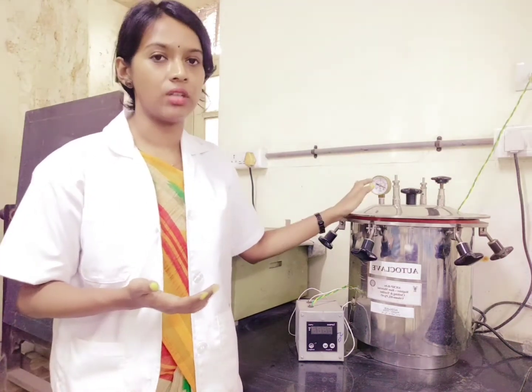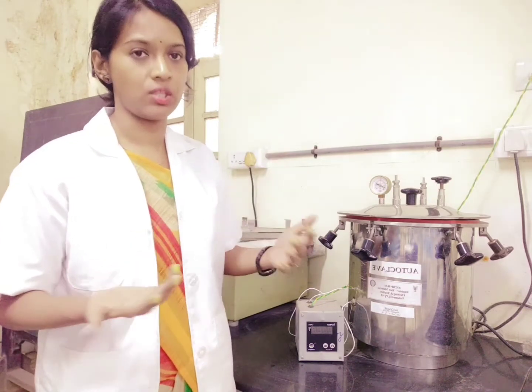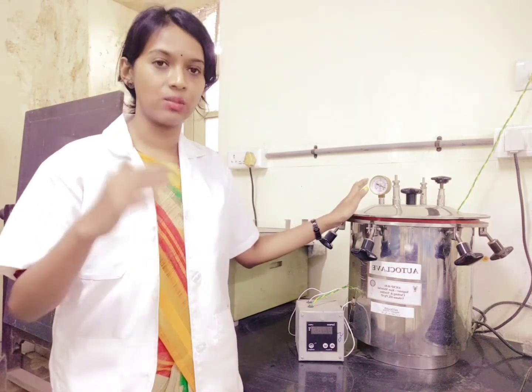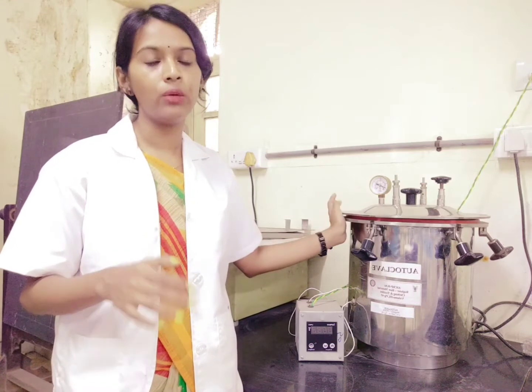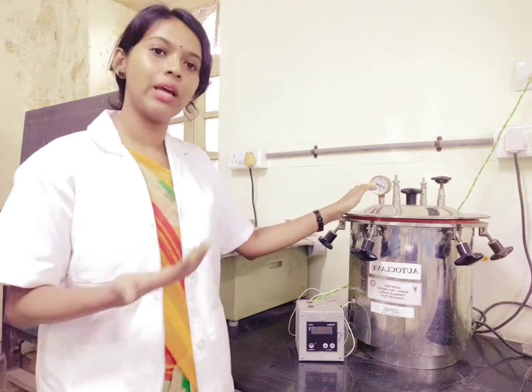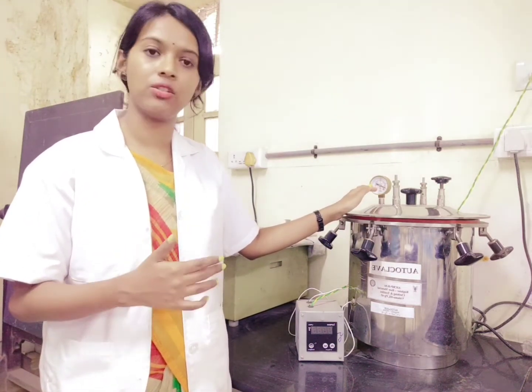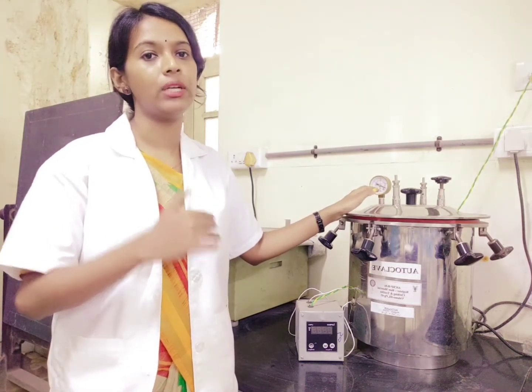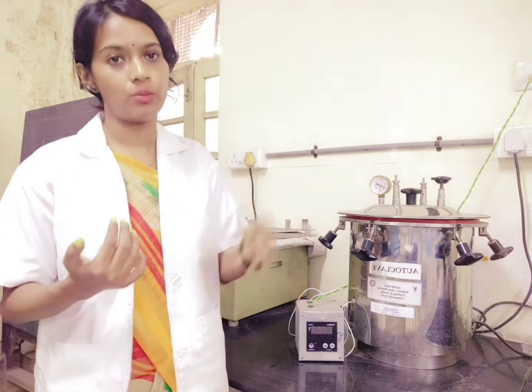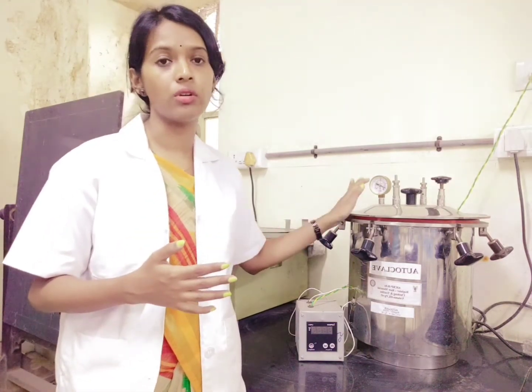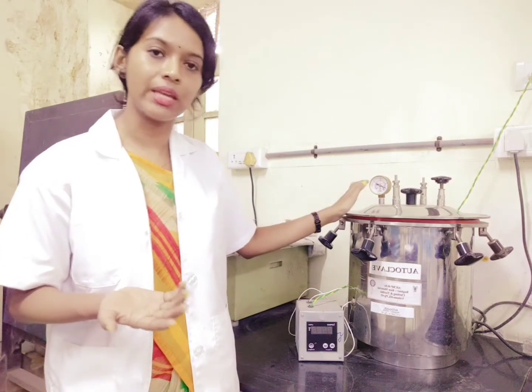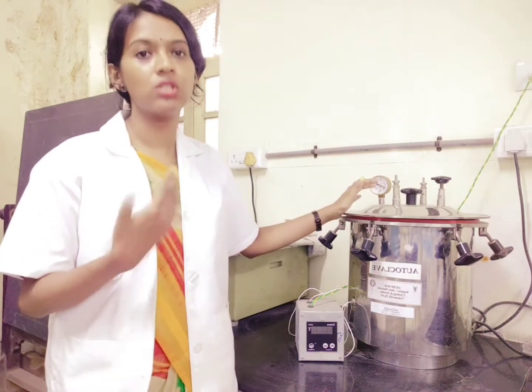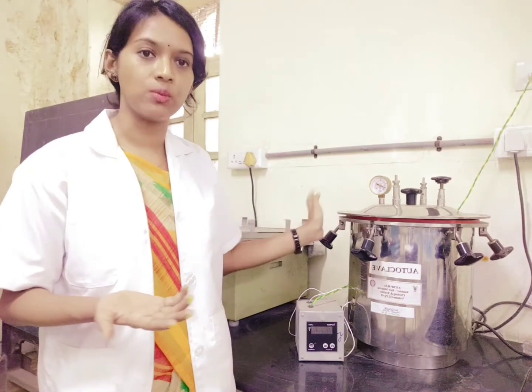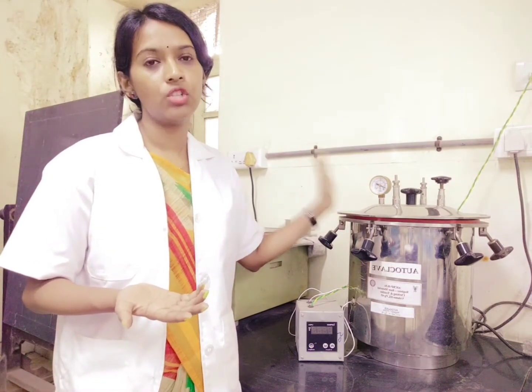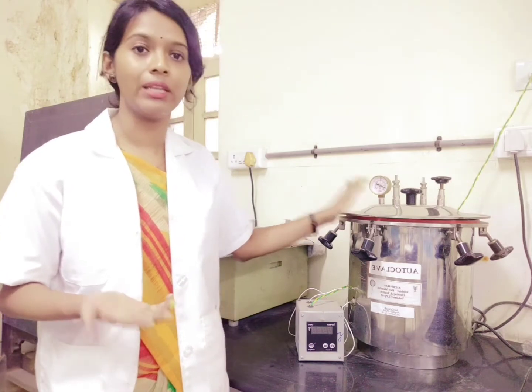Then in the second stage, the sterilization process takes place. In the purging stage, when the cool air is removed, it is occupied with hot air inside. Once that happens, the second stage starts, the sterilization stage, where the temperature and the pressure increase immensely. Because of this high temperature and pressure, the microbes present in the sample or inside the autoclave get destroyed. In the third stage, exhausting takes place. That means the pressure which has accumulated inside will be released.